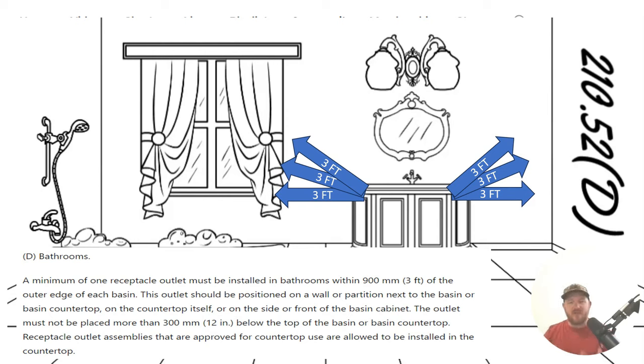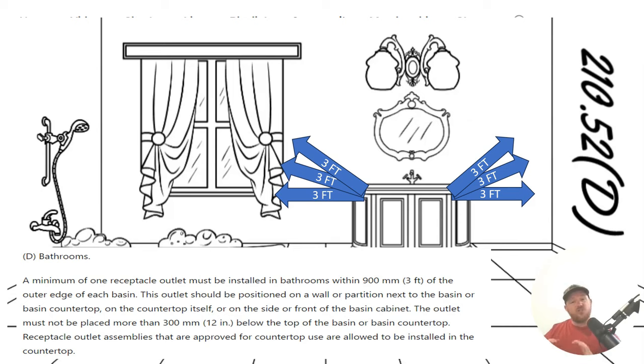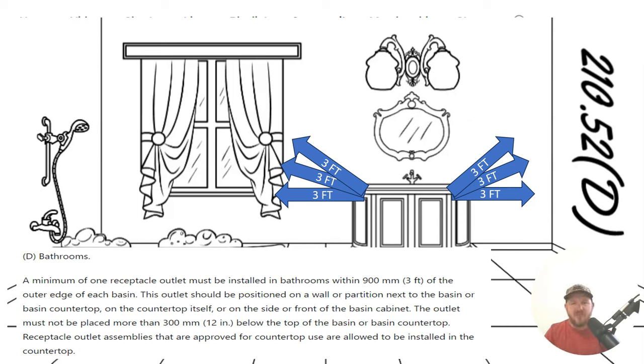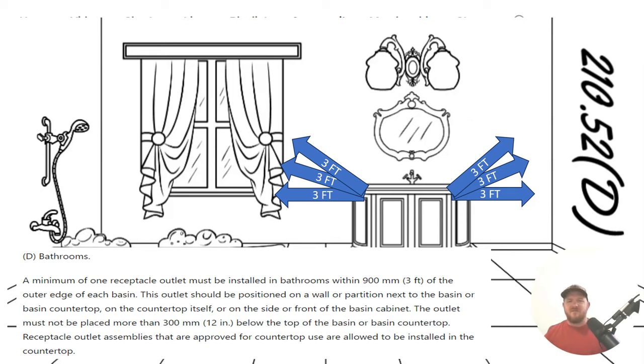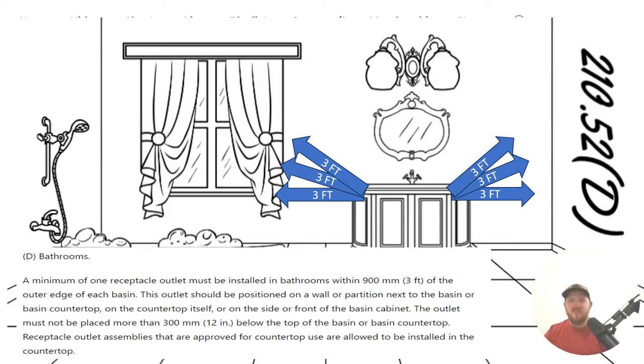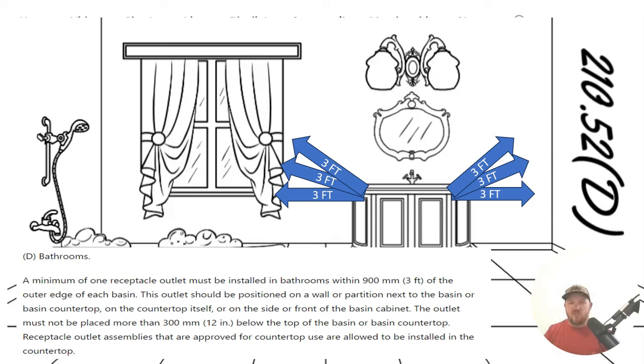If we have multiple basins, that measurement starts all over again. We are allowed to strategically place one outlet to satisfy the three feet for both basins. That's OK, because here it says three feet of the outer edge of each basin. So it doesn't say we have to have one outlet per, but it says that we must have an outlet within three feet of each basin. And this is to keep people, again, like we learned yesterday from running extension cords, especially in bathrooms.